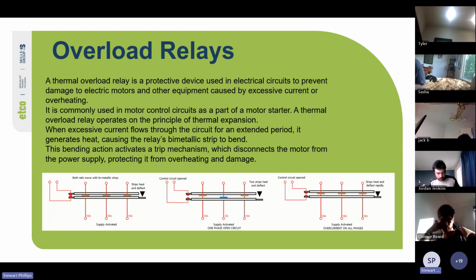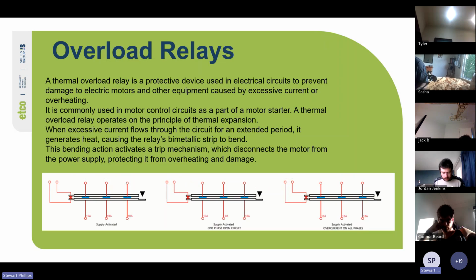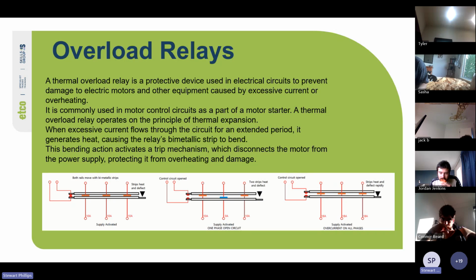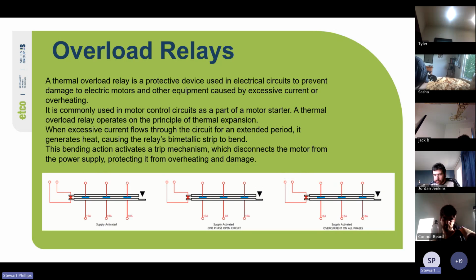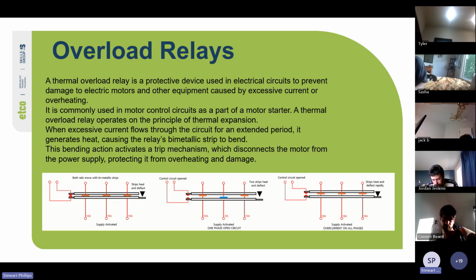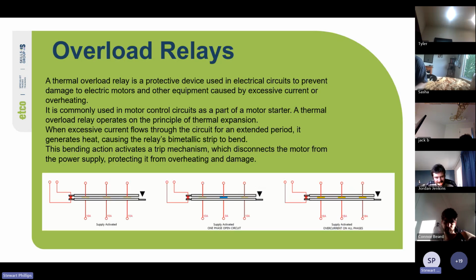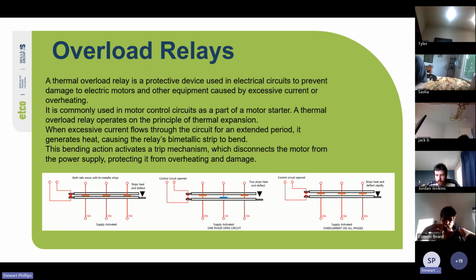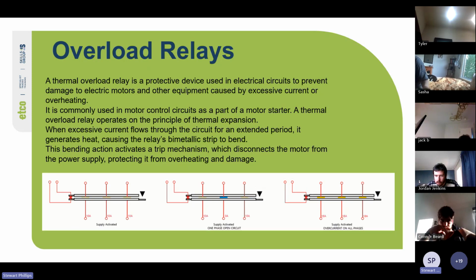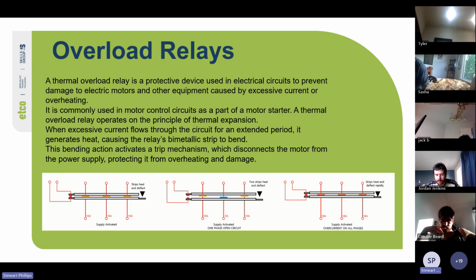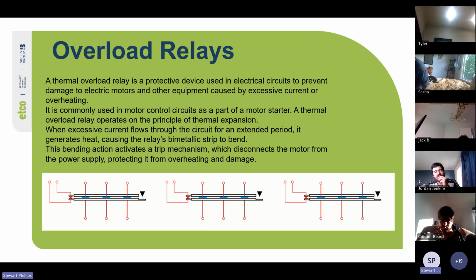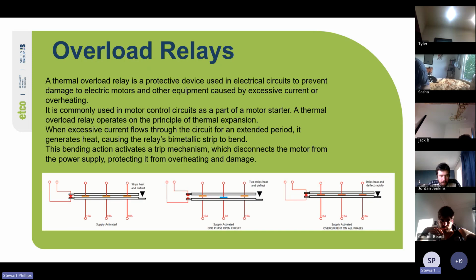Cool. So a thermal overload relay is a protective device used in electrical circuits to prevent damage to electric motors and other equipment caused by excessive current or overheating. It is commonly used in motor control circuits as part of a motor starter. A thermal overload relay operates on the principle of thermal expansion. When excessive current flows through the circuit for an extended period, it generates heat, causing the relay's bimetallic strip to bend. This bending action activates a trip mechanism, which disconnects the motor from the power supply, protecting it from overheating damage.